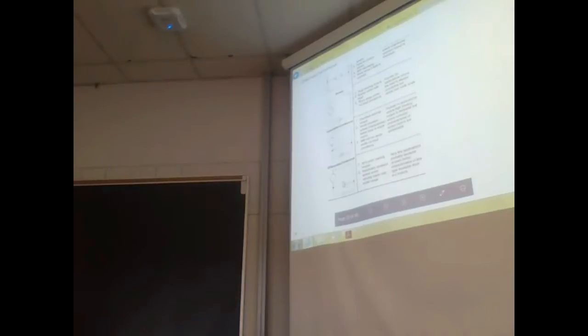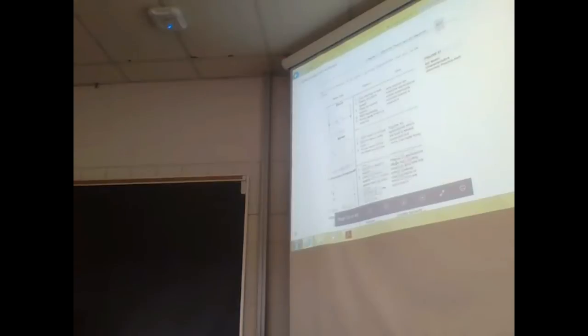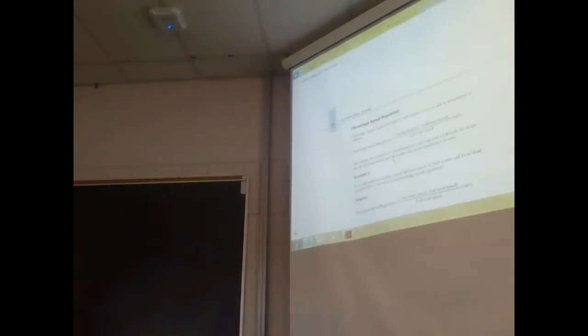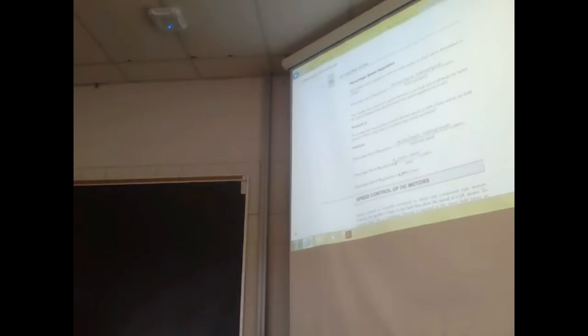Speed regulation behaves with respect to load and is termed similar to the generator. Percent speed regulation is no load speed minus full load speed, divided by the full load speed, times 100%. The smaller the variation in speed between no load and full load, the better the speed characteristic, and the nearer the speed regulation is to zero. And examples there.